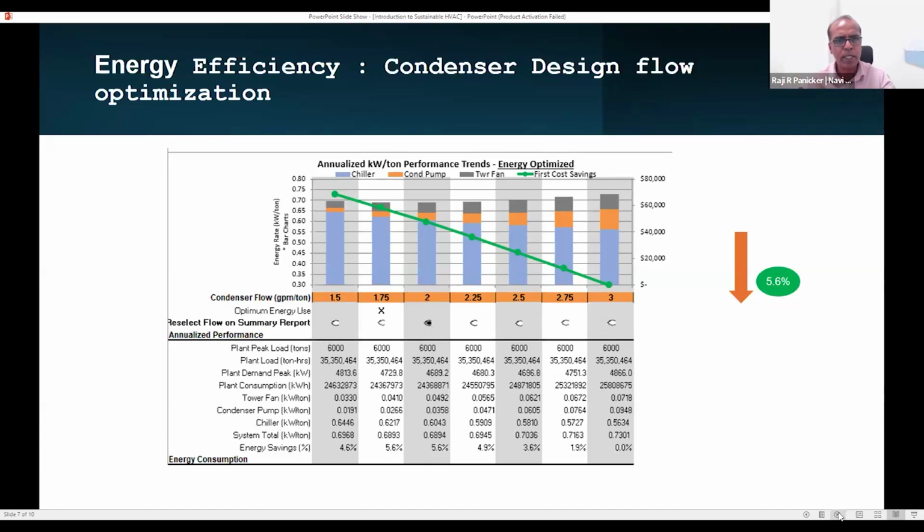Let's say I adjust my DRV to 3 GPM per ton, and with a variable frequency drive, I need to readjust it to 2 GPM per ton. So it's a fixed load, because varying it won't serve any purpose. You have to keep it at a fixed load, and everything related to condenser efficiency has to be taken from the condenser performance chart, which is readily available from the vendor, and you can use a linear equation to calculate this.